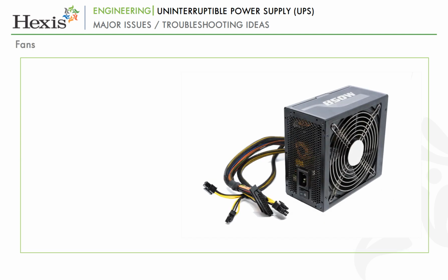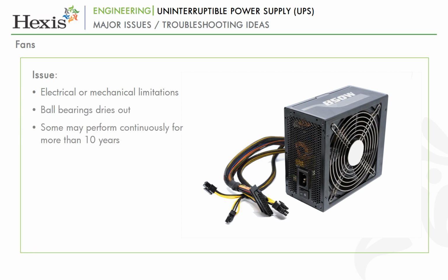The fans may fail due to their own electrical or mechanical limitations or when their ball bearings become dried out. Some fans may perform continuously for more than 10 years, while others may run only for short periods before locking up for mechanical reasons.